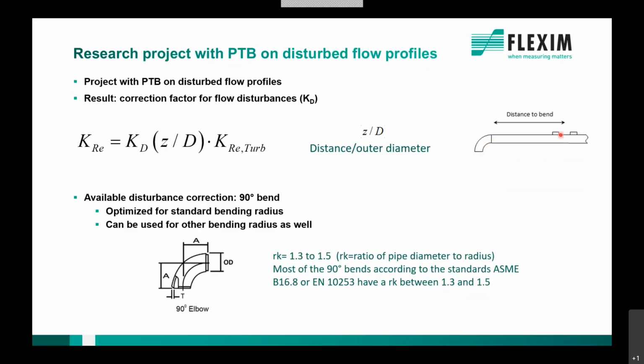And what you do is basically just measure the distance, z, from the middle of the transducers to the end of the disturbance. That means the straight length that is available, that is what you measure and enter in the setup. So it becomes part of the setup, is stored and used. The flow meter basically calculates automatically the inner diameter that we have in straight length, far away from the disturbance, uses that in the formula and corrects the disturbance automatically, based on the results from the PTB.